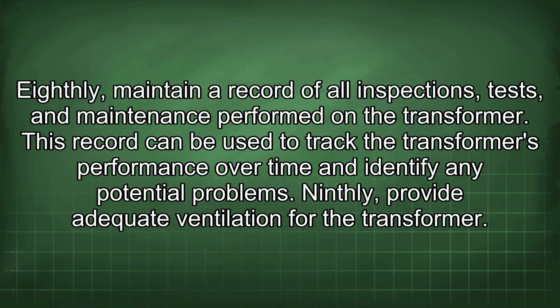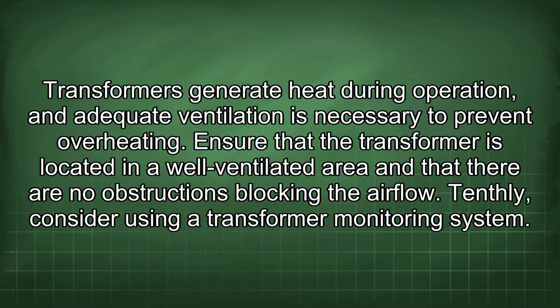Eighthly, maintain a record of all inspections, tests, and maintenance performed on the transformer. This record can be used to track the transformer's performance over time and identify any potential problems. Ninthly, provide adequate ventilation for the transformer. Transformers generate heat during operation, and adequate ventilation is necessary to prevent overheating. Ensure that the transformer is located in a well-ventilated area and that there are no obstructions blocking the airflow.